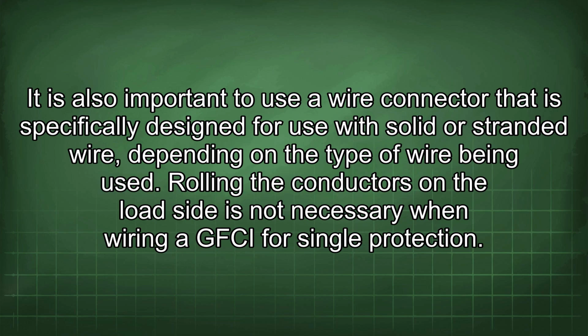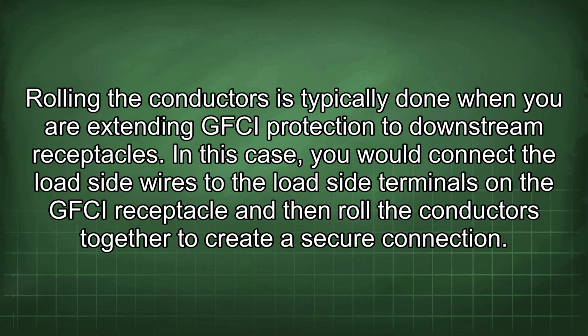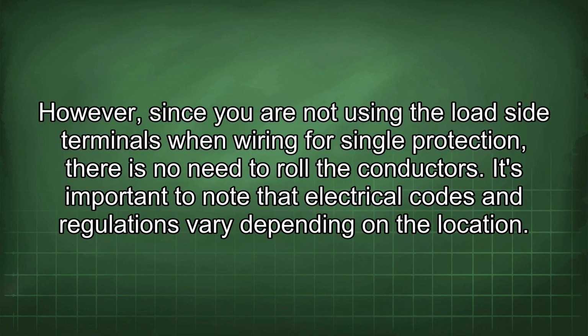Rolling the conductors on the load side is not necessary when wiring a GFCI for single protection. Rolling the conductors is typically done when you are extending GFCI protection to downstream receptacles. In this case, you would connect the load side wires to the load side terminals on the GFCI receptacle and then roll the conductors together to create a secure connection.